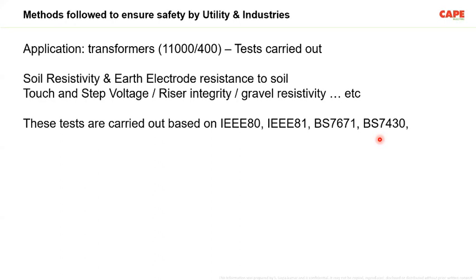I don't know why our engineers, Indian engineers, always want to go behind the American and the British standards in order to test an Indian installation. Actually, the Indian standards are much clearer and much better. I would like to explain a small example. In America, the electricity distribution to houses is HVDS, high voltage distribution system. What it means is, on the right side, you can see I have put a transformer with a 20 kV input supply and 120 or 240, 120 phase to neutral and 240 phase to phase supply to the consumer premise.